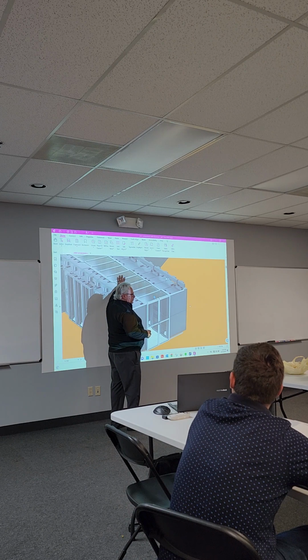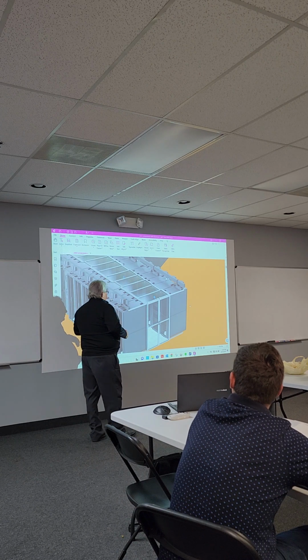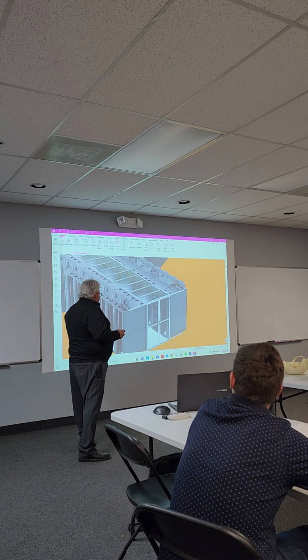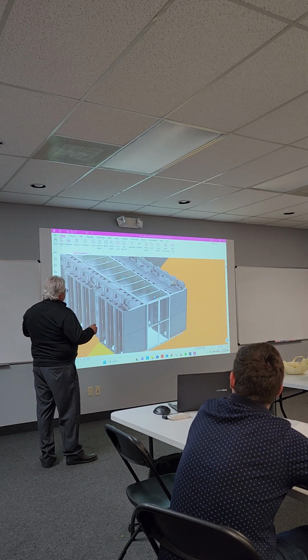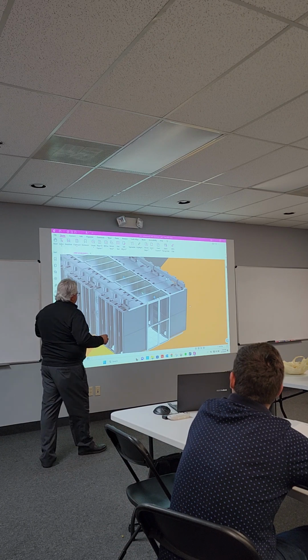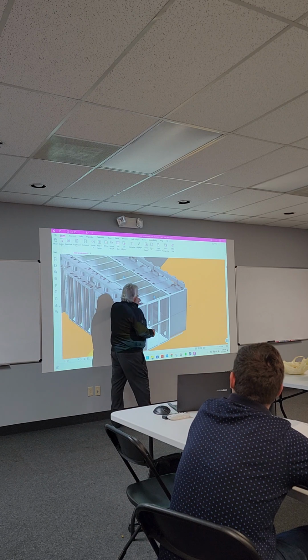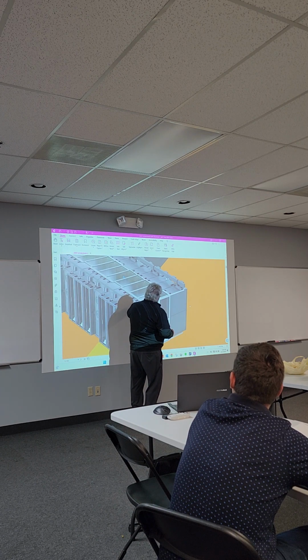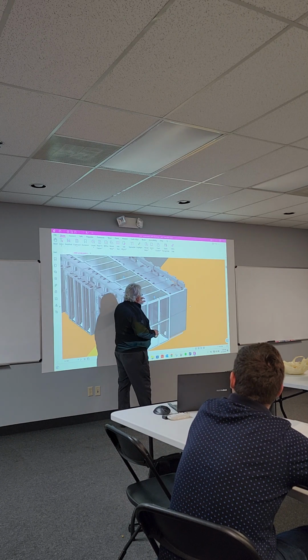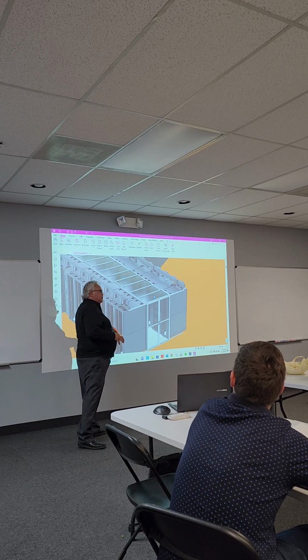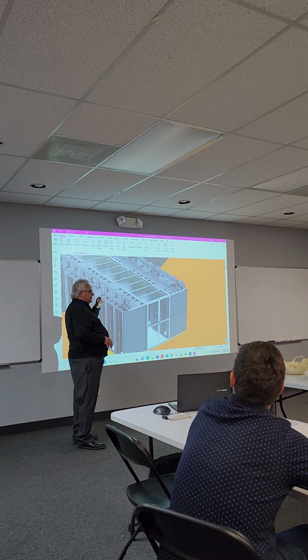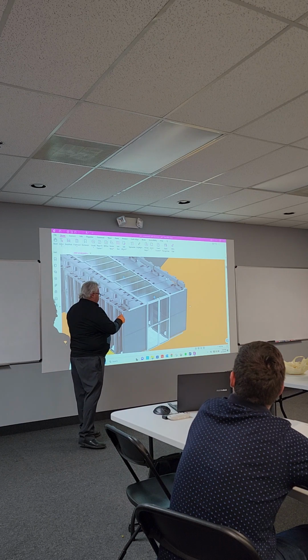A lot of these rooms have sprinklers and whatnot, so depending on where they are and what type of fire suppression they're using, we have to take that into consideration. These panels are made of like plexiglass, but on these ends, if the temperature gets above 130 degrees, the panel actually falls away from the aluminum, it melts and shrinks and falls so the fire suppression can work. Some fire codes say that's okay, some want it to be instantaneous, so they don't want you to use this.